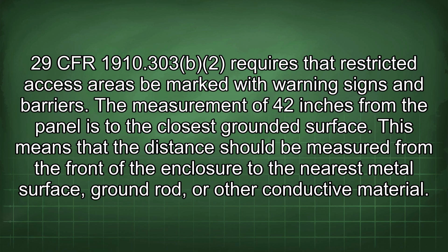29 CFR 1910.303 requires that restricted access areas be marked with warning signs and barriers. The measurement of 42 inches from the panel is to the closest grounded surface. This means that the distance should be measured from the front of the enclosure to the nearest metal surface, ground rod, or other conductive material.